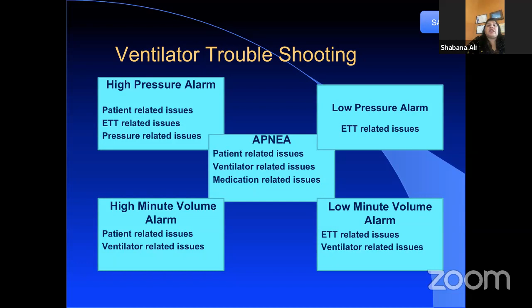And then comes the apnea alarm. With the apnea alarm, the patient is not breathing at all: either the ventilator has shut off, or the patient is not breathing, or the ventilator parameters are too low to affect the patient. So all the high alarms are related to the tubing on our patients most of the time, or the ventilator, and the low is always related to a leaking side, that something is going out of the system. Next slide. So what is the best care that we can do?